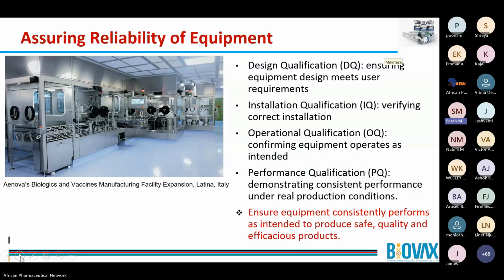And this performance qualification is similar to what you'd do for the annual or biannual calibration. So this is a very important qualification, because if it doesn't meet this requirement, then you cannot commission the equipment. So we need to ensure that the equipment consistently performs as intended to produce safe, quality, and efficacious products. So if you get it wrong at the equipment level, you cannot rely on those results. So you need to ensure that the entire qualification is done.